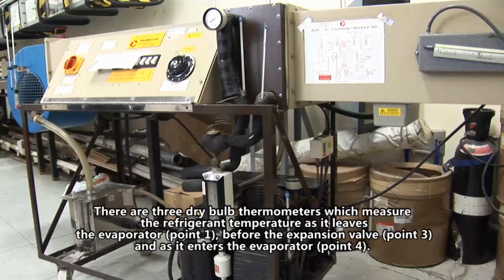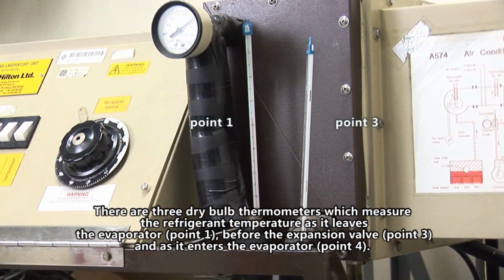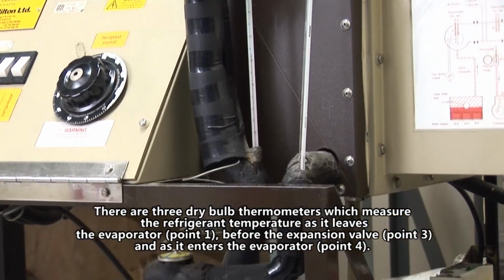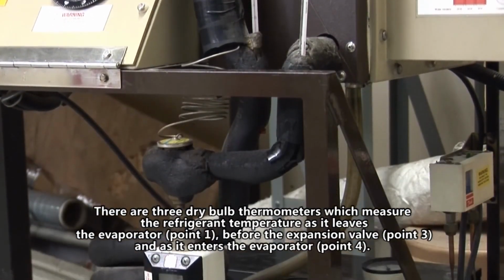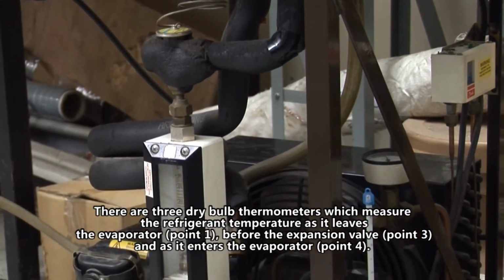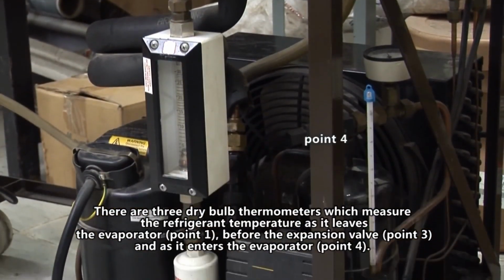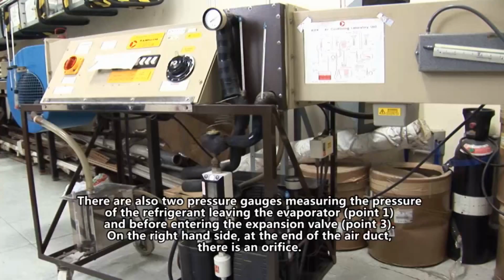At the bottom of the unit are the compressor, condensing unit, and the thermostatic expansion valve. There are 3 dry bulb thermometers, which measure the refrigerant temperature as it leaves the evaporator, point 1, before the expansion valve, point 3, and as it enters the evaporator, point 4. There are also 2 pressure gauges measuring the pressure of the refrigerant leaving the evaporator, point 1, and before entering the expansion valve, point 3.